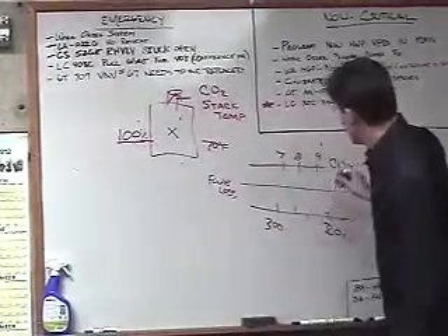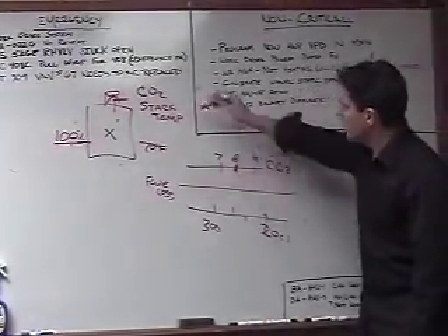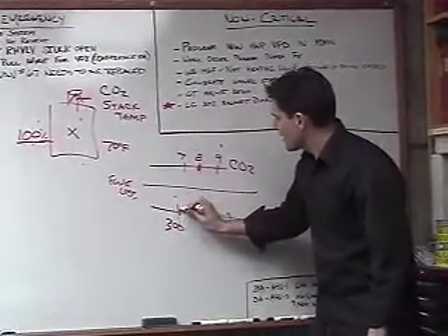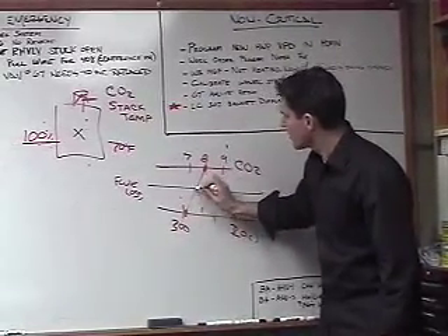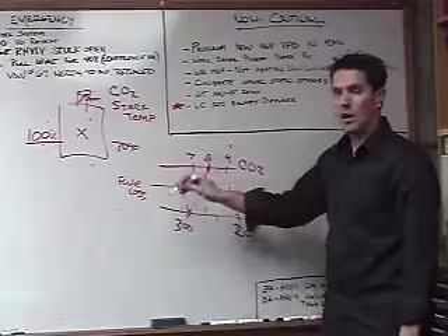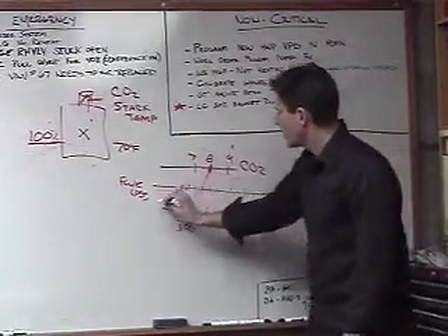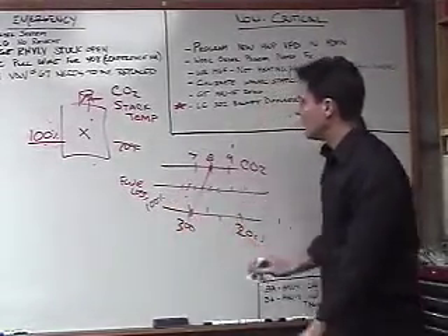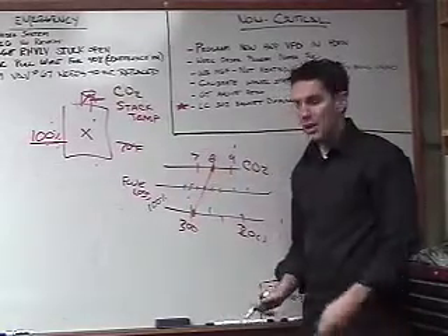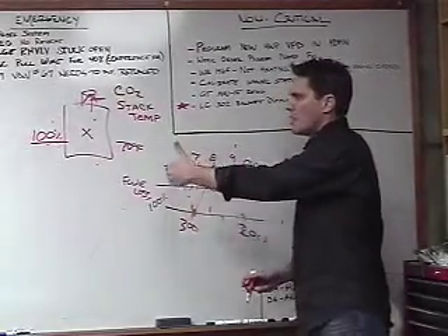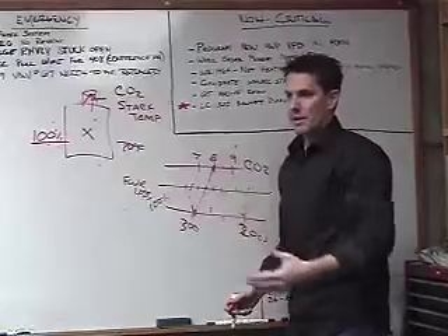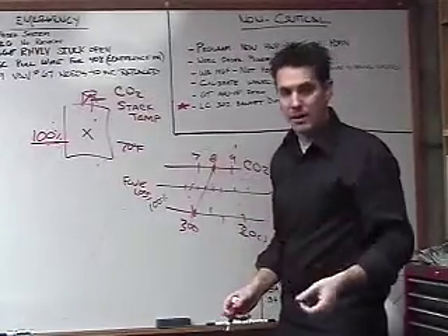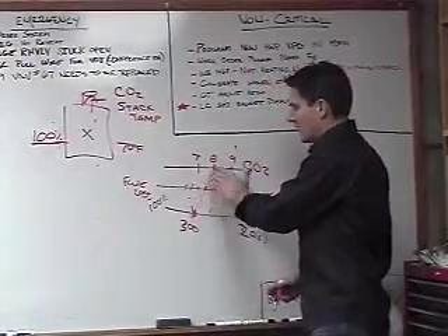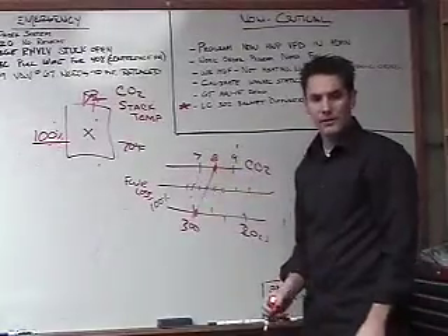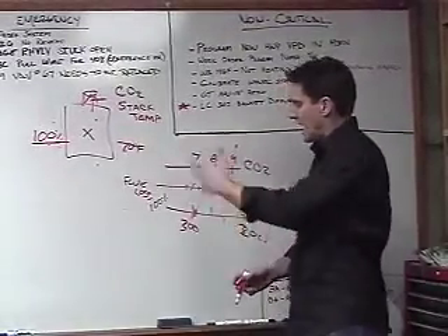Okay, so what we would do is we'd say, okay, I've measured an 8% CO2, and I'm measuring here. We draw a line wherever I cross. That would tell me what my flue loss is. We'd subtract that from 100%, and that would give us our combustion efficiency. Nowhere in here does it say, well, do that at 20% firing rate, do that at 80% firing rate. It's one point, and it tells you what your combustion efficiency is. Okay, so ANSI tells me how to do that.